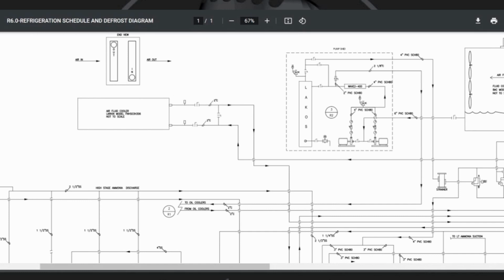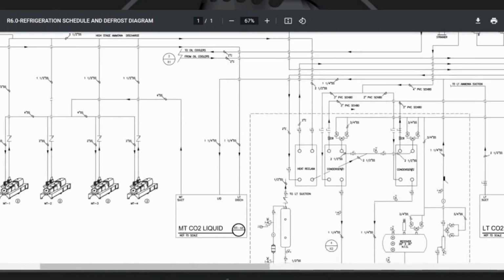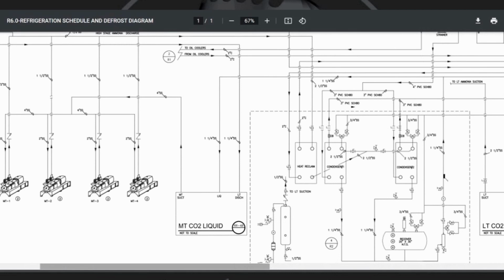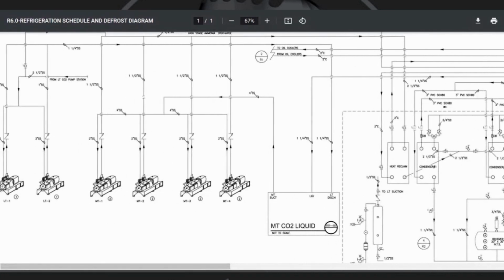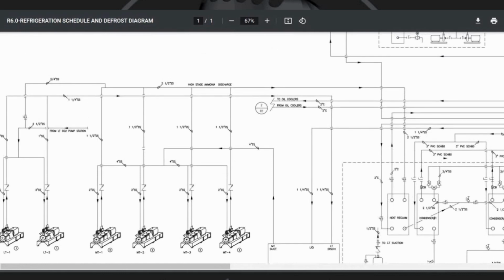Probably the one thing that some of these people might be interested in is the energy efficiency of this system, and it's not quite as good as our standard direct drive two-stage synthetic system. It's about 6 or 7% less efficient, and the reason is very simple. We have to run the compressors at 10 or 12 degrees colder because of the inefficiency in the thermal siphon. So we're losing considerable energy there.